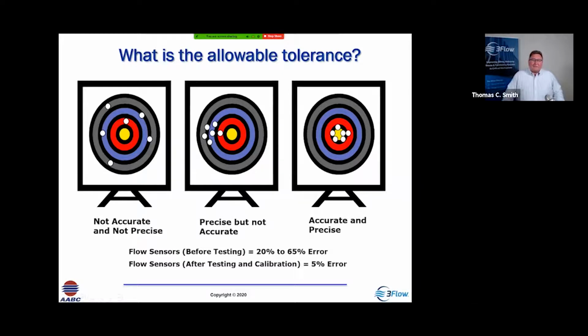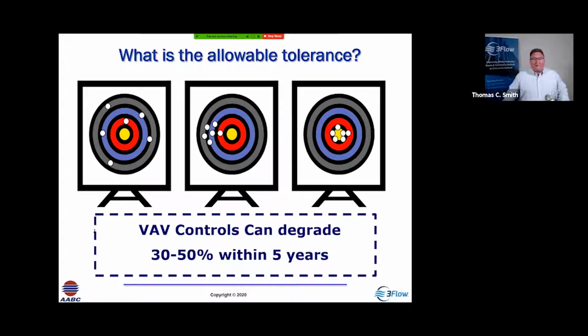I can tell you we've done tens of thousands of hoods, VAV, and oftentimes we see significant errors. What we'd like to see is less than 5% error between the measured value and the reported value from the monitors and the building automation system. We also see that without proper testing and maintenance, VAV controls can degrade 30 to 50% within the first 5 years. Normally the fume hoods get tested and fixed, but the general exhaust and the supply are generally disregarded. And after 4 or 5 years, we've got significant problems that create air balance issues and failure to meet the needs of the occupants.